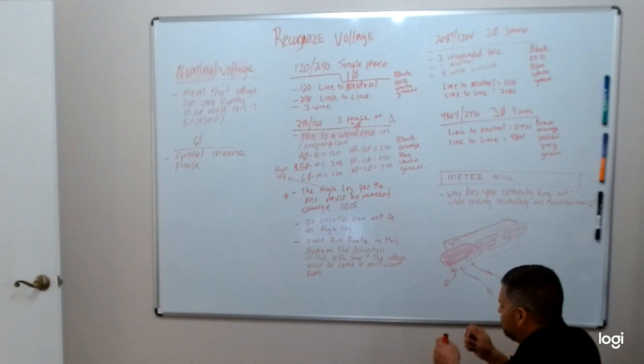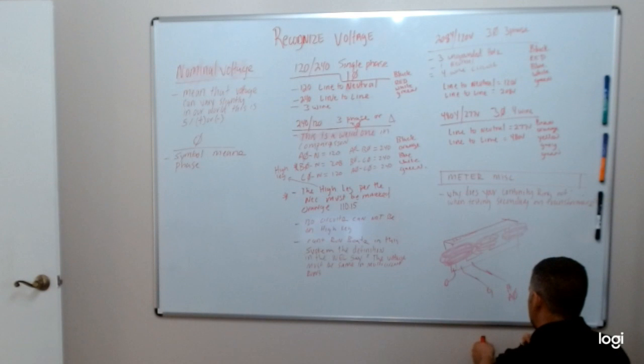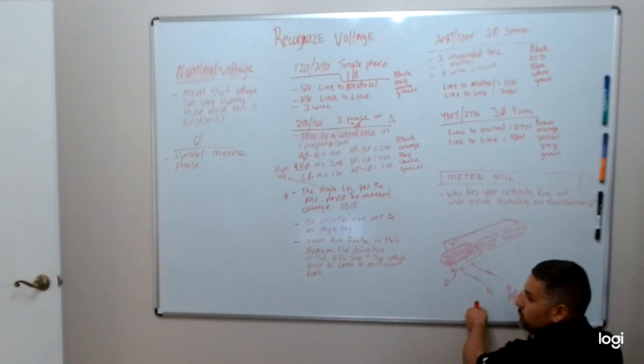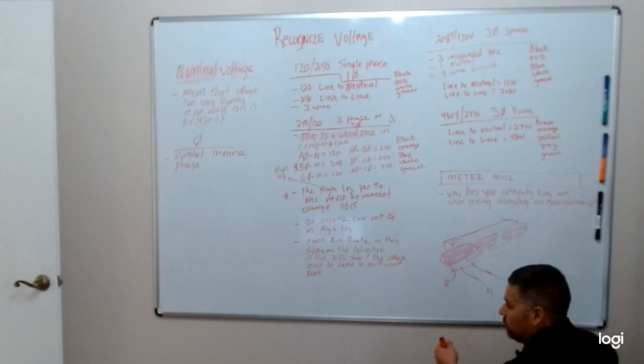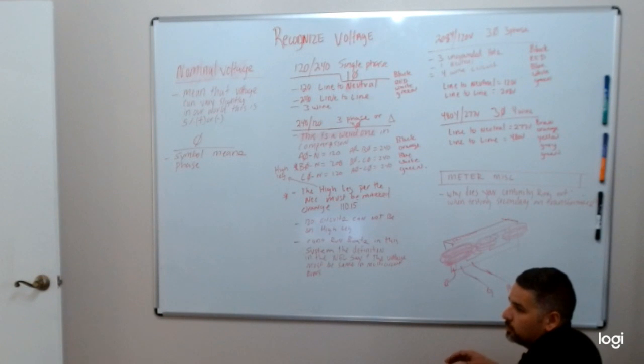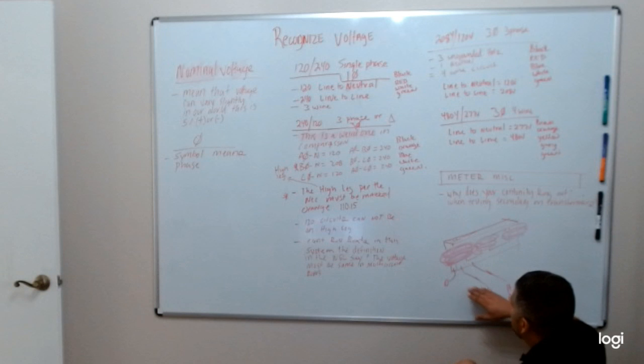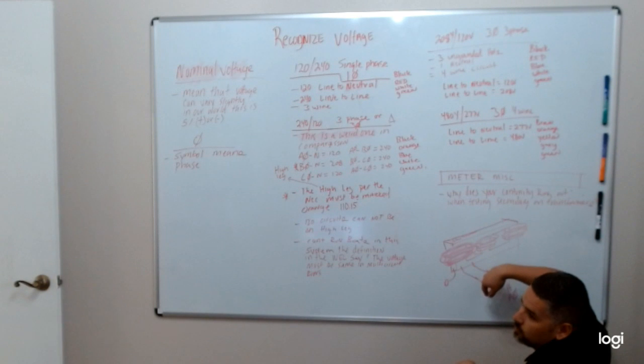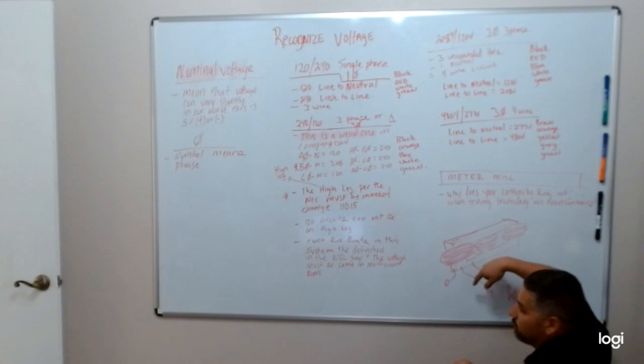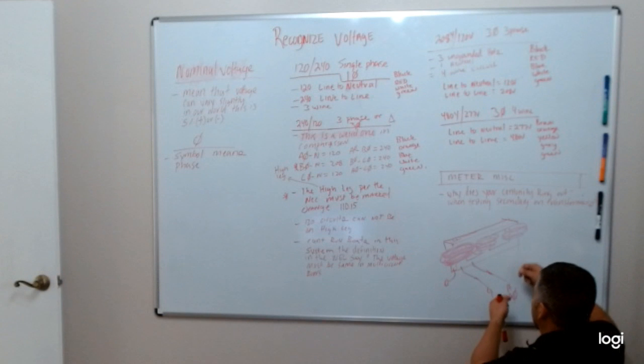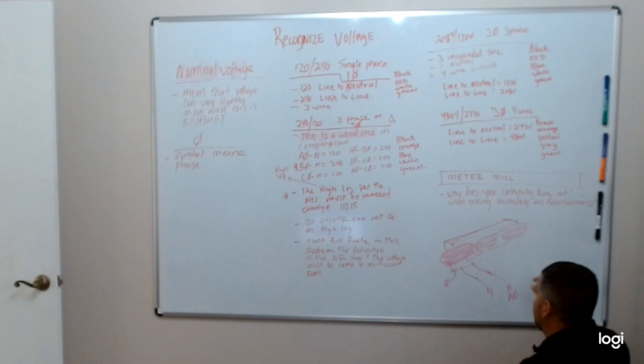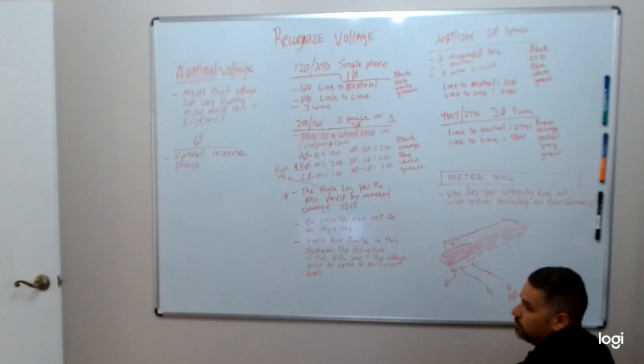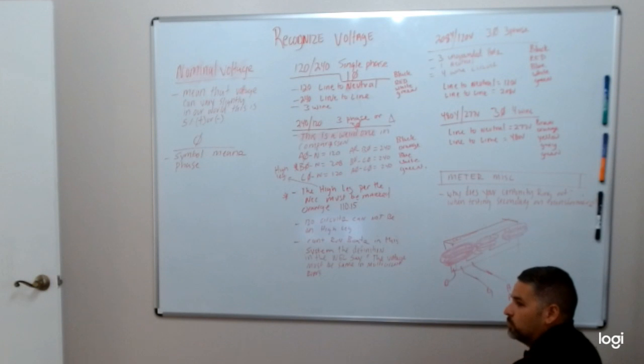So if you put your continuity tester, red and black, you put the black on the ground, and then you're trying to see if this thing is ringing out. And you do this primarily when you're testing your new wire setup to see if there's an issue pulling the wire in, essentially. And you're like, oh shoot, I want to make sure that this thing's clear of any faults. So if you already have it hooked up, it's going to read continuity and scare you, because you're like, oh no, it's ringing out. But then you'll go to B phase and C phase and see that those are ringing out too, and it's because they're all connected. Everything's connected inside the transformer, bringing that voltage down.